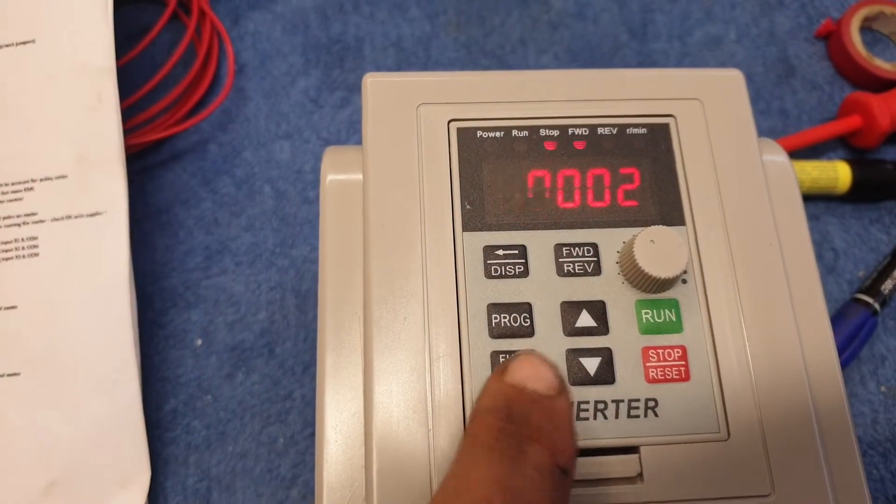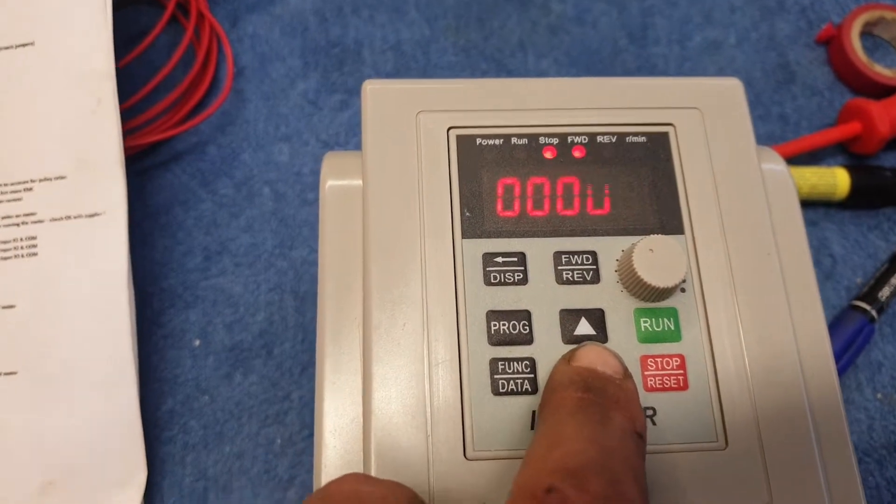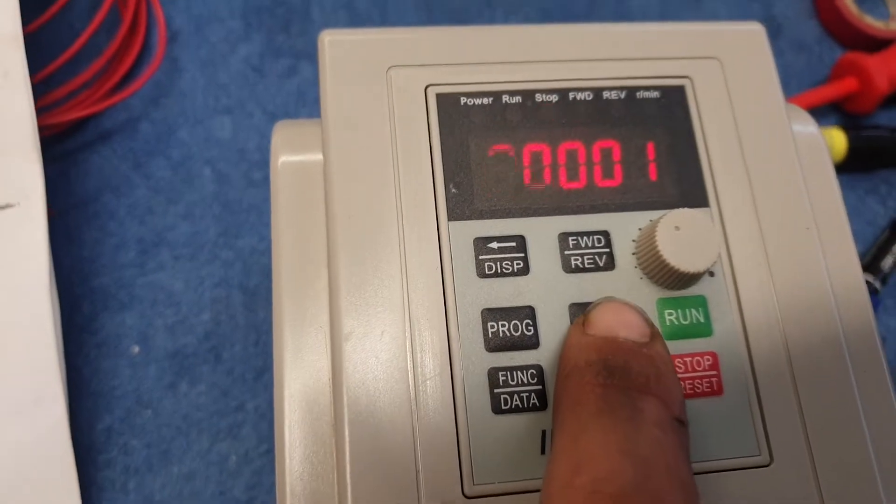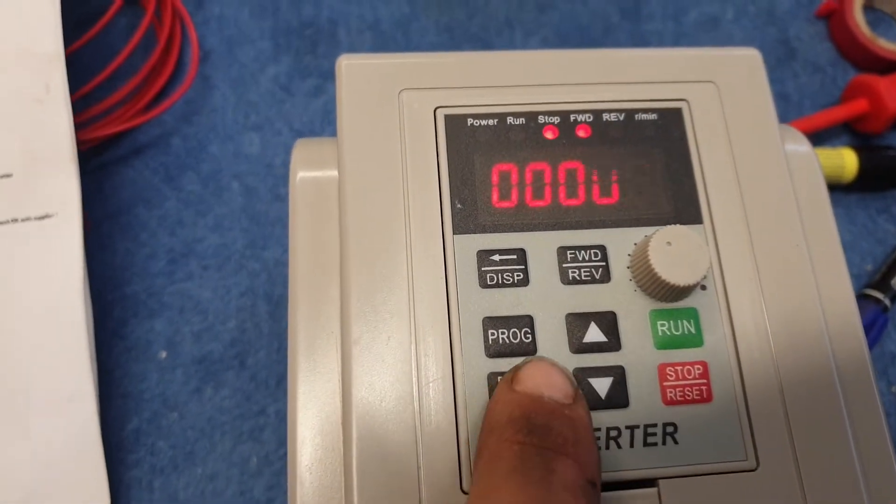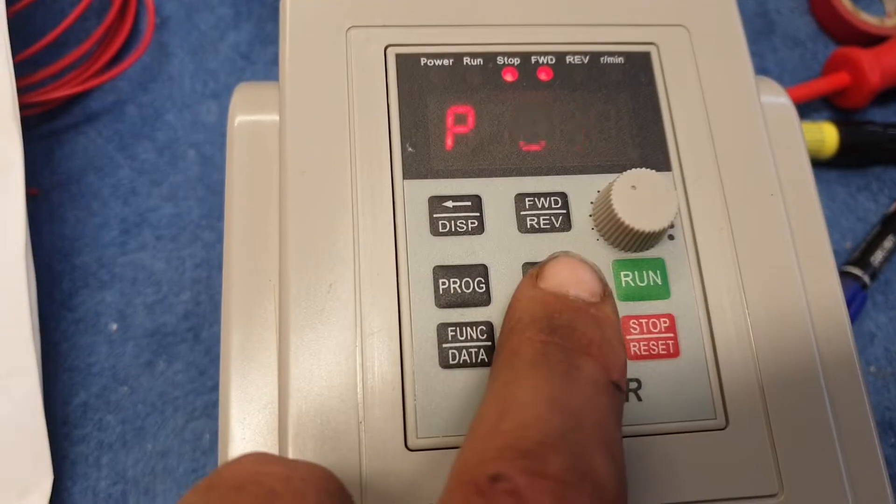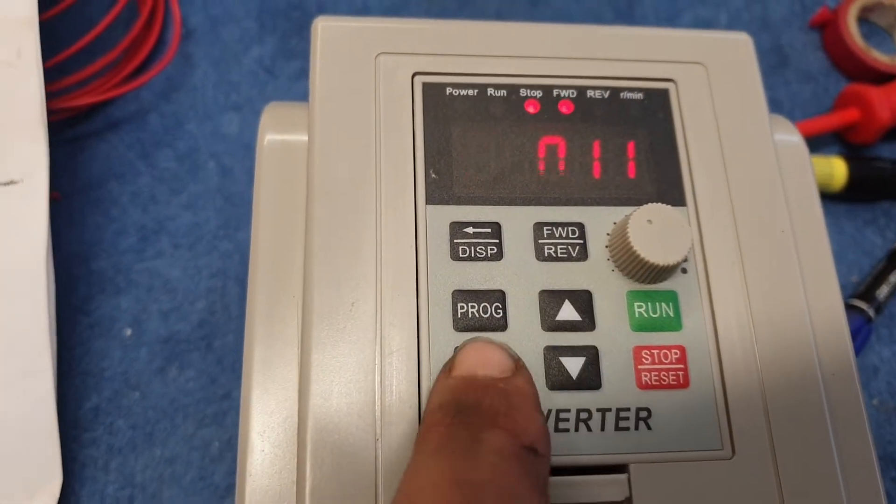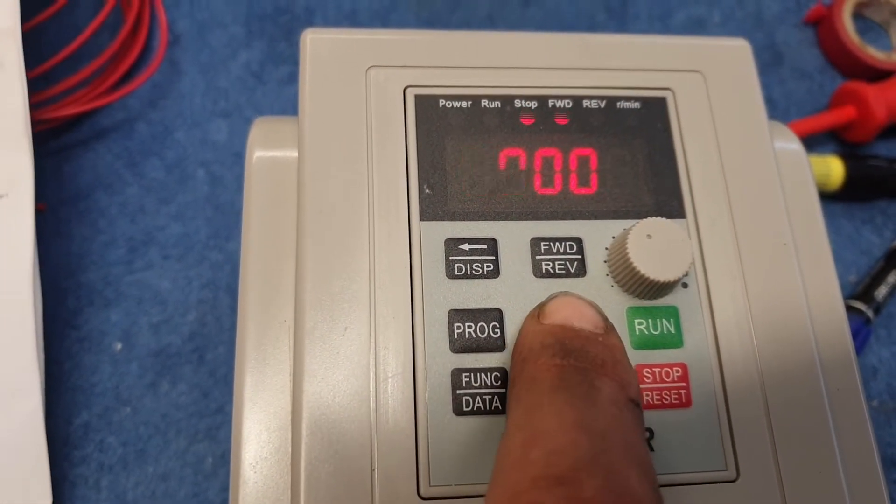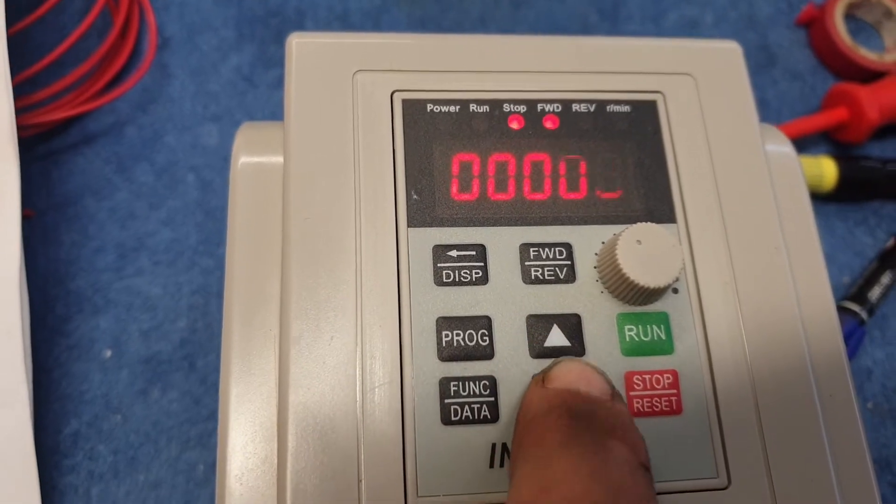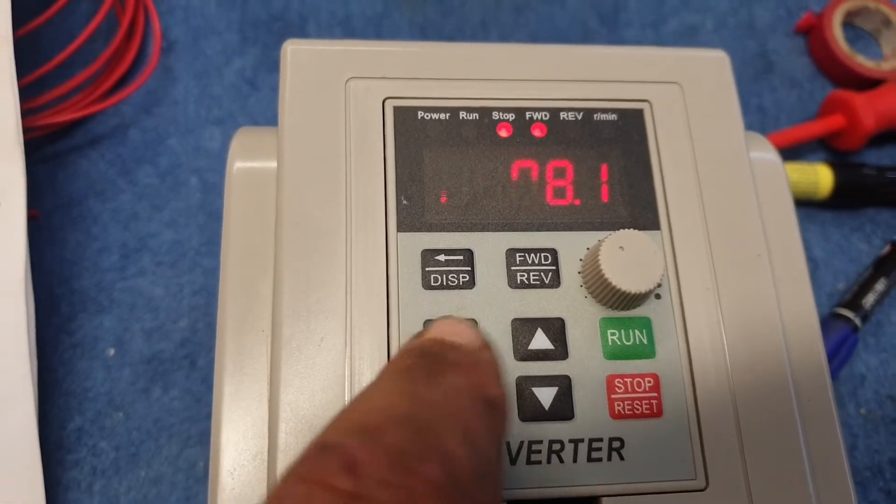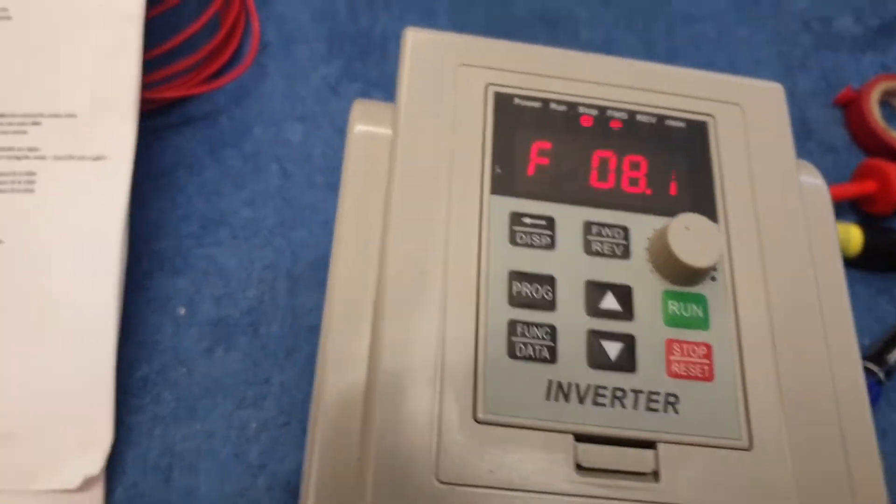Go into function, and by default it's set to one, you have to set it to two. Press function data. Program 11 is how you start and stop it. You set that to two. By default it's set to zero, but you set it to two. That's it. Press program again and you're good to go.